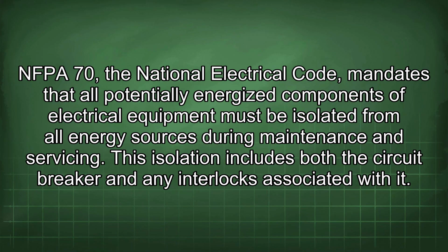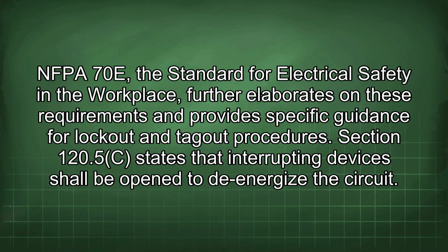NFPA 70, the National Electrical Code, mandates that all potentially energized components of electrical equipment must be isolated from all energy sources during maintenance and servicing. This isolation includes both the circuit breaker and any interlocks associated with it. NFPA 70E, the standard for electrical safety in the workplace, further elaborates on these requirements and provides specific guidance for lockout and tagout procedures. Section 120.5c states that interrupting devices shall be opened to de-energize the circuit.